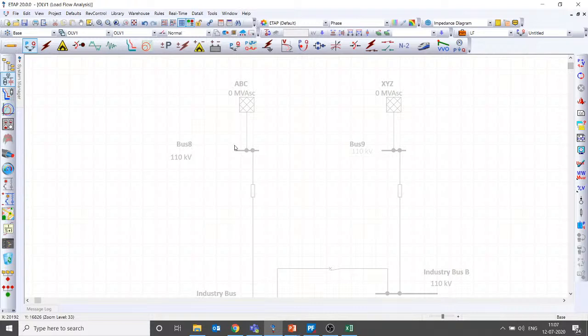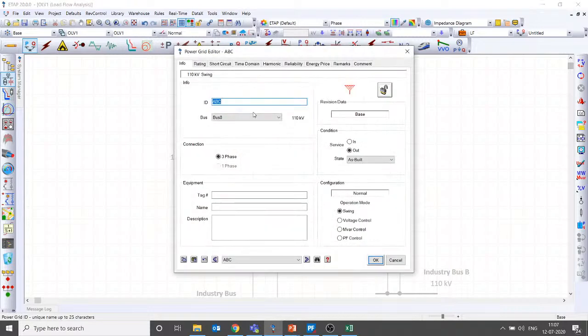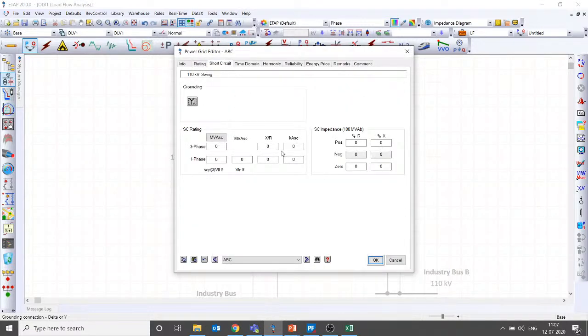Voltage and phase angle is more relevant to the load flow, which decides how much real and reactive power is flowing. And for the short circuit, I have not even given the three phase current and single phase current, I have given it as 0. So it is immaterial. Even if you know three phase short circuit current and single line to ground fault current, you will not be able to find out the voltage and angle. So I believe that is clear, Sasikumar. I believe this is the question you expected me to answer.